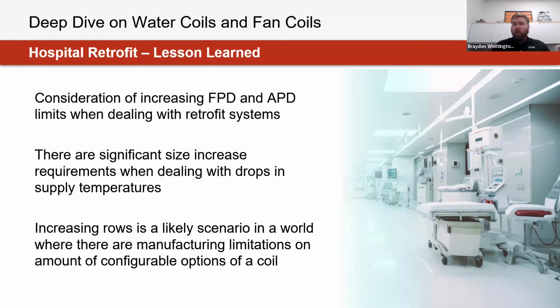We can't just bump up the size of coil because it's probably going to be much bigger. That's not going to match the existing footprint or ductwork that's likely within those systems. So a likely scenario that we're really going to see, especially when looking at terminal retrofits or fan coil retrofits, is that you're going to have some limitations in terms of what circuitry or fin density adjustments you really can make. In a lot of cases, this is going to be an adjustment of rows, but again, some considerations just for how much adjustment of our targets there will be for fluid pressure drop as well as for air pressure drop.